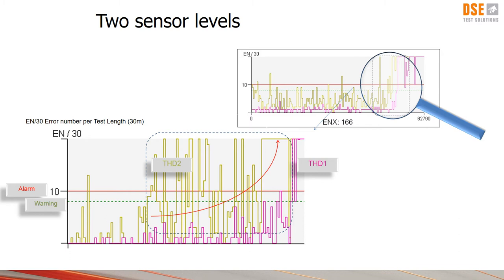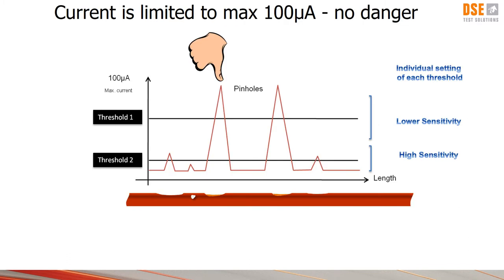This note, to be able to use threshold 2, a certain speed of the line is needed. I better remember to say that the high voltage sounds dangerous, but only combined with current. The system is safe to use and without dangers for the operator, because the maximum current is limited to 100 microamps.